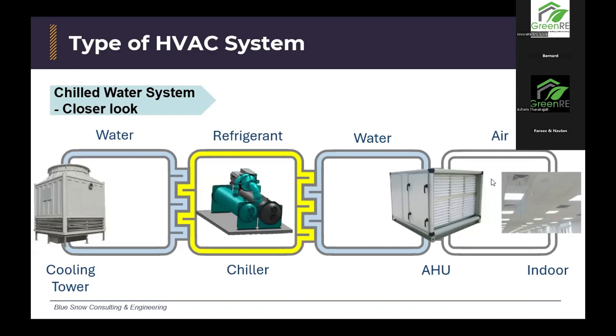Okay, this one is just an example of a chill water system, where we start with the air. Different from the direct refrigerant system, where there are only four main components and only one loop, which is the refrigerant loop, here there are four main components, and the first one is the air, which is our ambient indoor space. So the same process, where the indoor air that has the heat goes to the AHU, or air handling unit, and inside the AHU there is a coil as well, but instead of refrigerant, the coil is filled with water. Now we're entering the water loop.